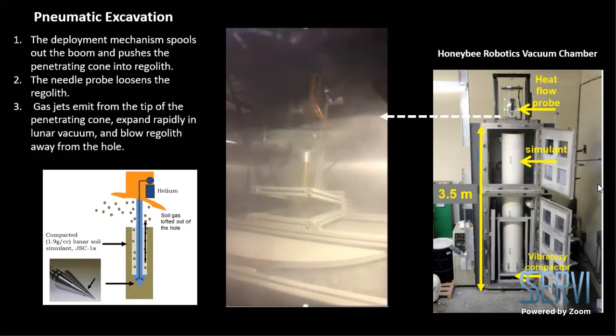So here, the picture on the right is how we test this pneumatic drilling capability of Lister. Here we're using a 3.5 meter tall vacuum chamber set up at Honeybee Robotics. Inside we have a PVC tube that is filled with regolith simulant. Then the heat flow probe is set up at the top. We test the closed, sealed chamber, pump out, and then test the pneumatic drilling.